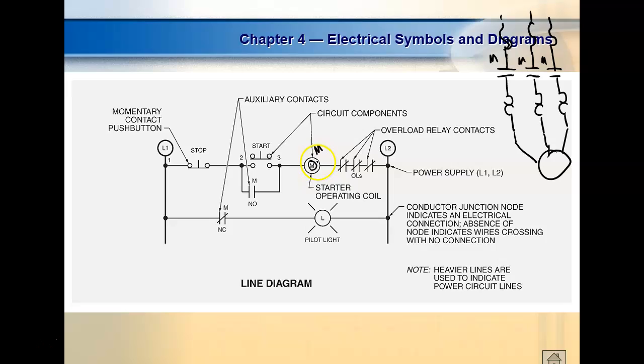So this is a relay coil. This is the coil. You can't say it's the relay. Why? It's the coil because the relay consists of two things. It consists of the coil and the contacts that are being controlled by the coil. Everybody okay? And we'll use the term energized. So if we say it's energized, it means that magnet has jerked those contacts and made them change directions.